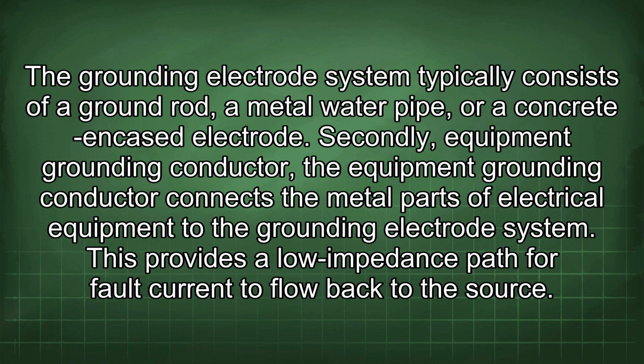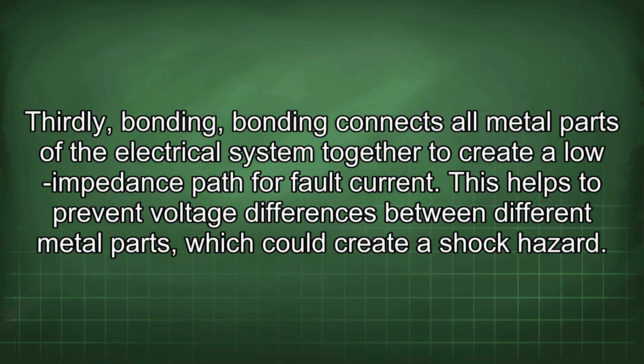Secondly, equipment grounding conductor. The equipment grounding conductor connects the metal parts of electrical equipment to the grounding electrode system. This provides a low impedance path for fault current to flow back to the source. Thirdly, bonding. Bonding connects all metal parts of the electrical system together to create a low impedance path for fault current. This helps to prevent voltage differences between different metal parts, which could create a shock hazard.